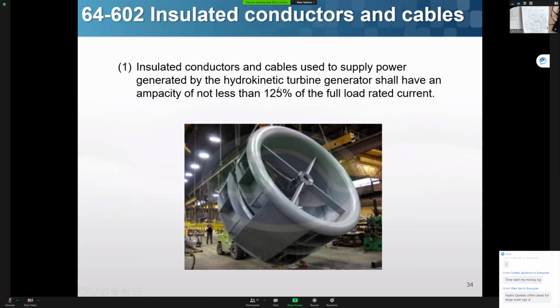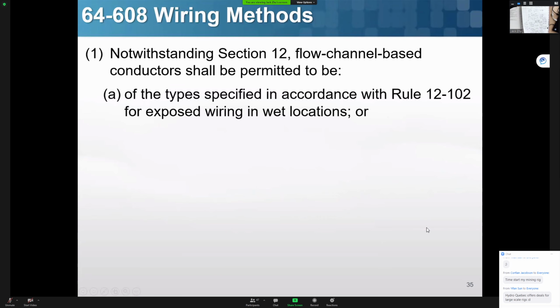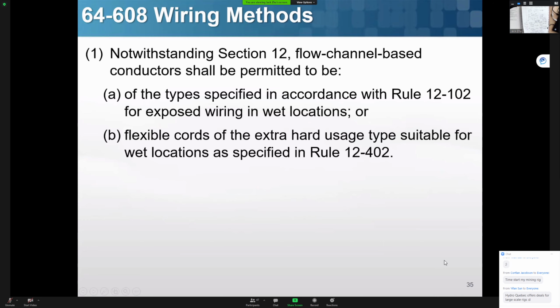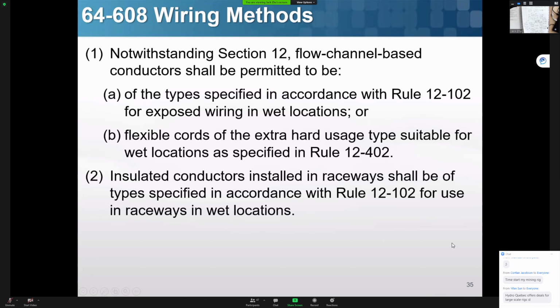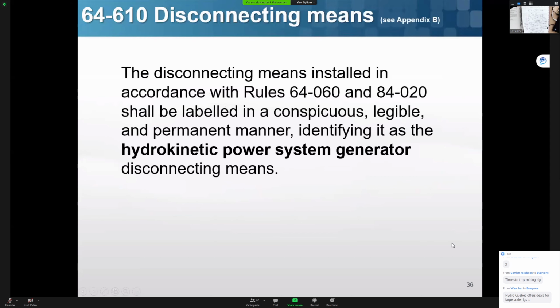For most of those renewable energy generators, the conductor has to have a capacity no less than 125% of the full load rated current. Wiring methods have to follow Section 12. As for what type of wire you can use, usually you have to use wire suitable for wet location. Disconnect means is always required. We know that. That's the electricians.